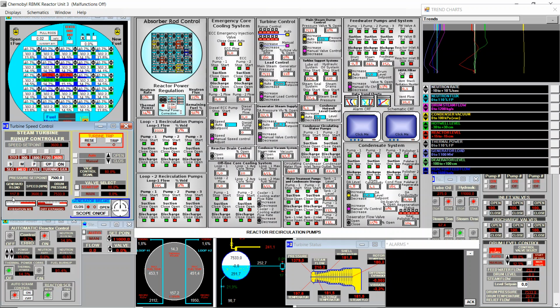Generated load, it's higher than before, it's at 113 megawatts, but it's oscillating, so we'll wait a bit for it to stabilize, otherwise we could incur a reverse load.